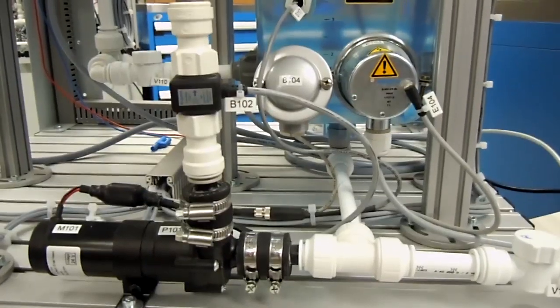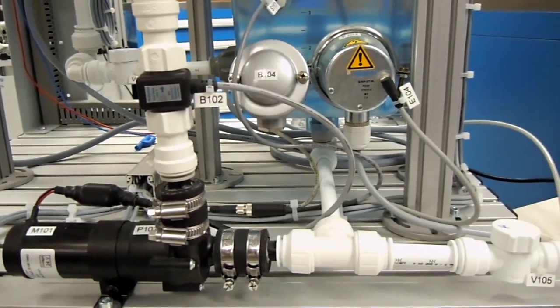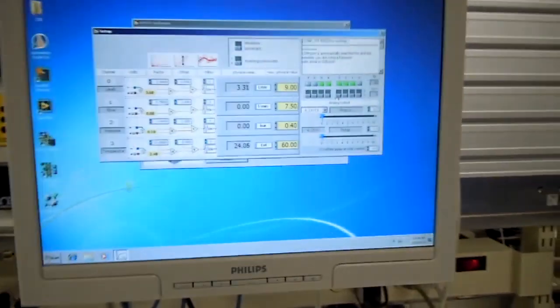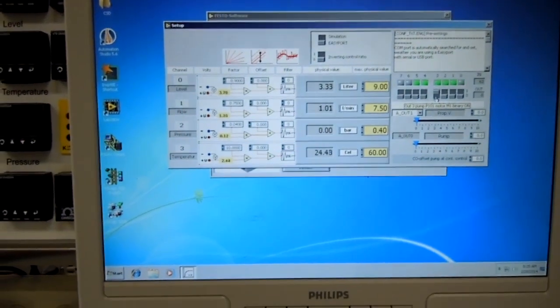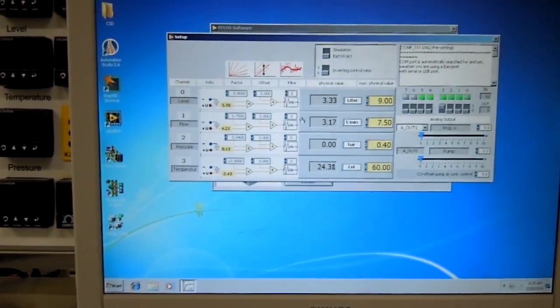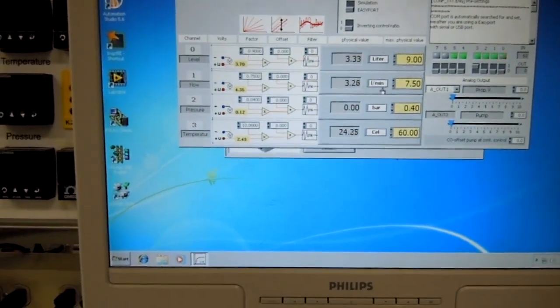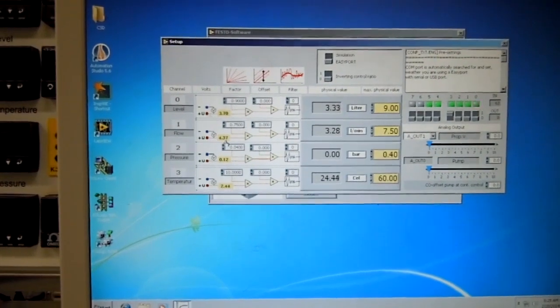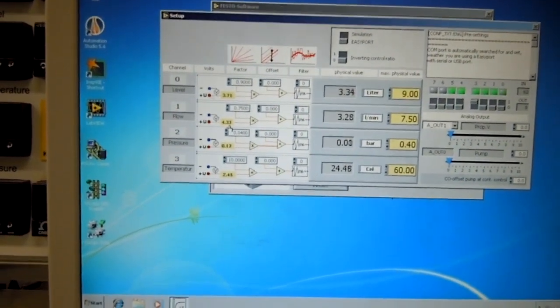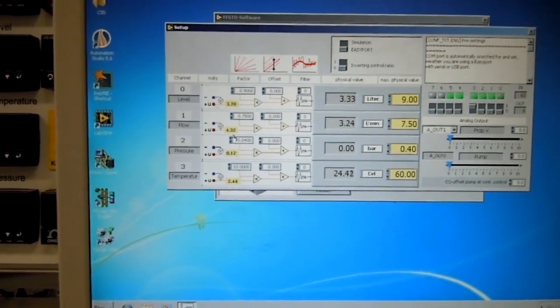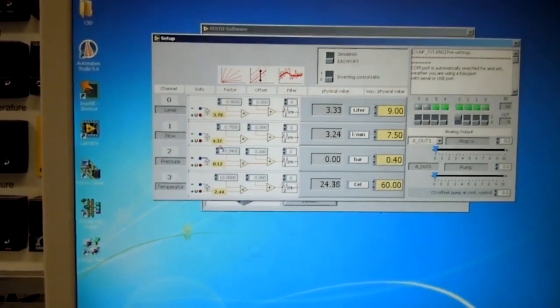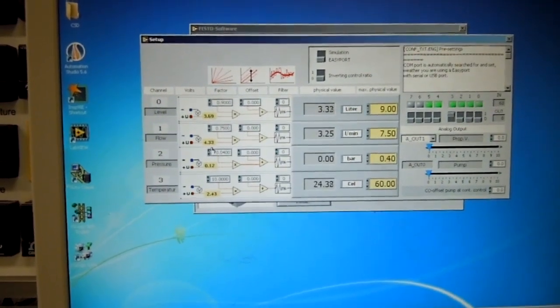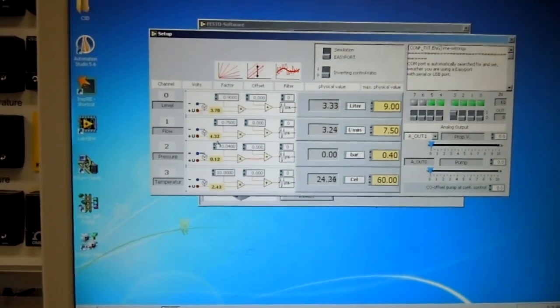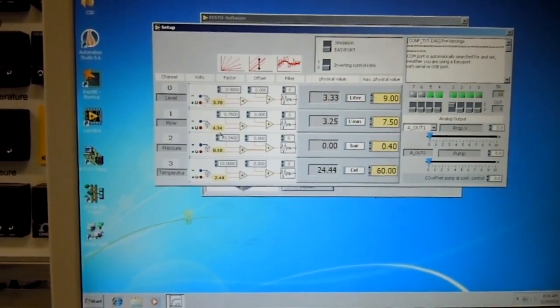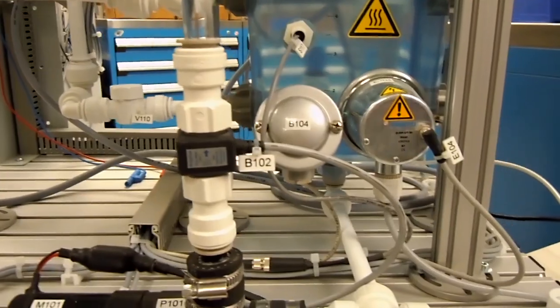Okay, so I'm just going to show you the operation of the flow sensor when we actually have some flow going into the tank. So coming back to the screen, I'm going to enable the pump motor. You can see I've just done that, and if you look at the screen, you'll see right here that I have some flow now. It's measuring this in liters per minute, but over here is the voltage where my mouse is pointing that shows you the voltage that I'm getting from my sensor. And recall that 0 to 9 liters of flow gives you 0 to 1200 hertz, but then you have a converter that converts the 0 to 1000 hertz to 0 to 10 volts. So I'm actually getting 433 hertz. From that you can figure out the liters per minute. So back to the workstation, you can see that there's flow in the top tank.